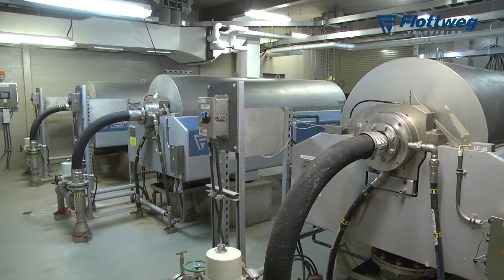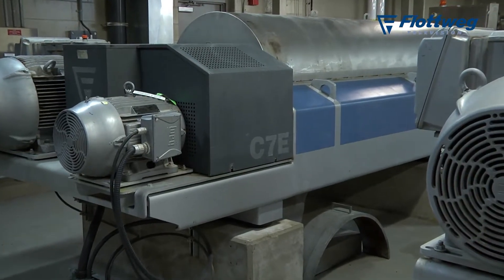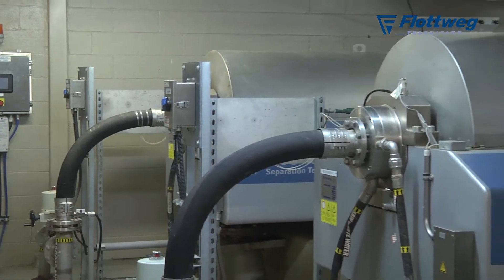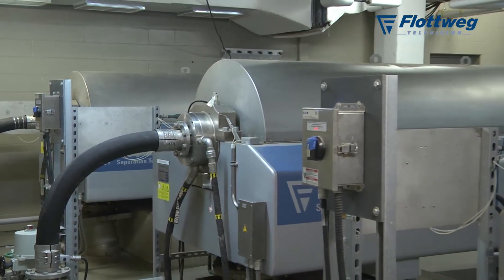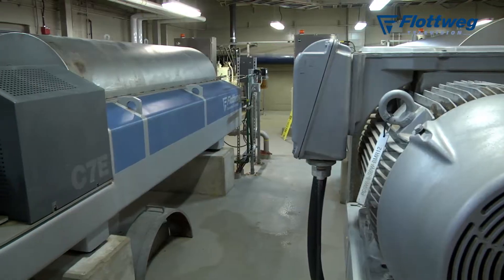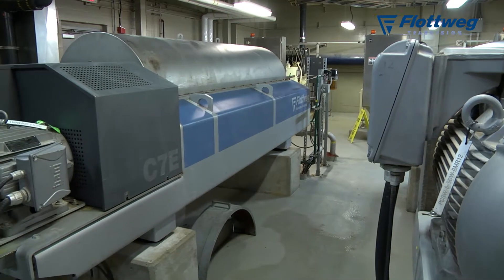We have three Flottweg C7E units installed here at Greenway. The process is operating 95 percent of the time and two of those units will be running at any one time. These three machines are individually designed to accommodate 1200 litres per minute of liquid flow or 1700 kg per hour of mass flow.